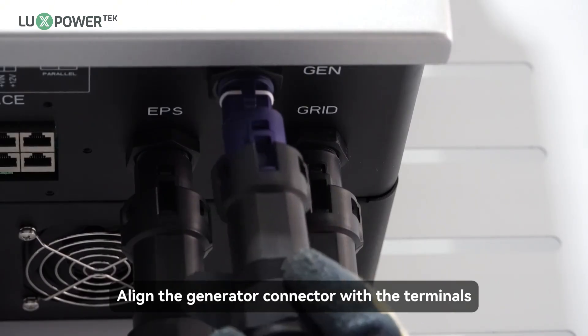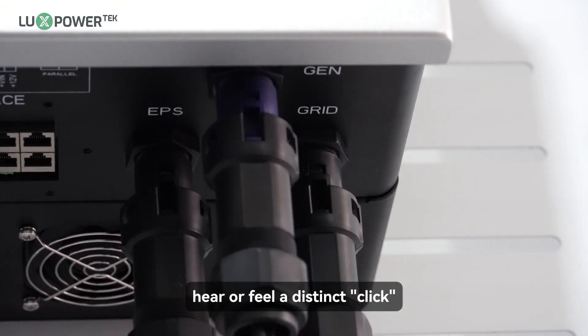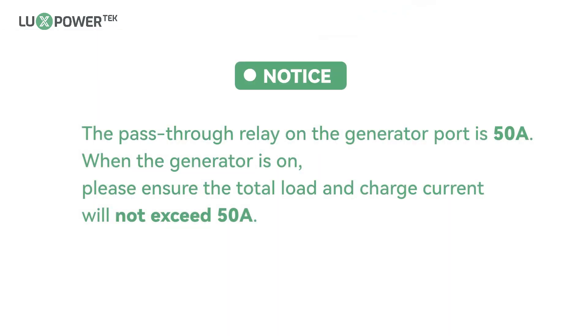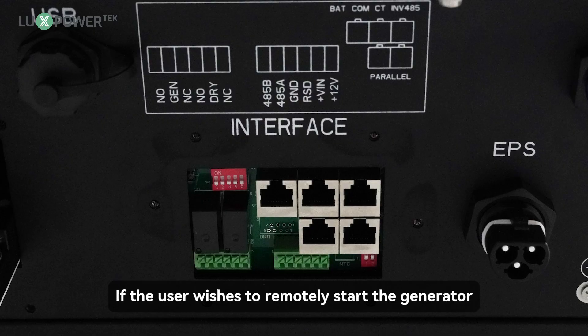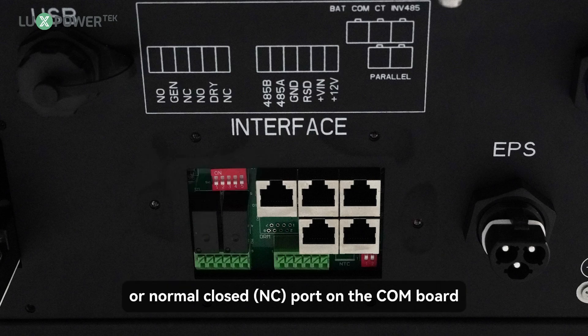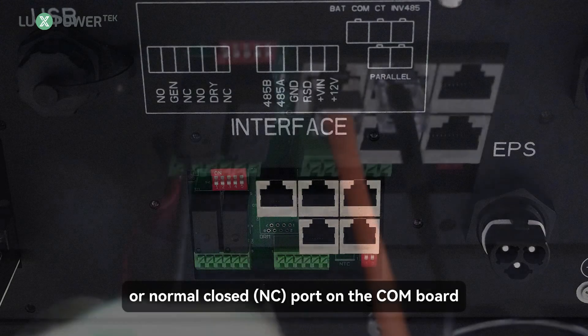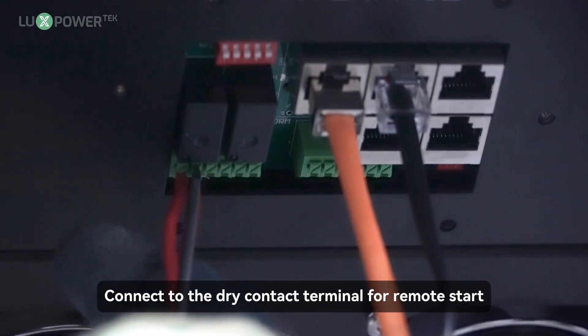Step 4: align the generator connector with the terminals and manually engage them until you hear or feel a distinct click. Notice: the pass-through relay on the generator port is 50A. When the generator is on, please ensure the total load and charge current will not exceed 50A. If the user wishes to remotely start the generator, the generator start signal should be connected to the GEN NORMAL OPEN (NO) or NORMAL CLOSED (NC) ports on the COM board. Connect to the dry contact terminal for remote start.